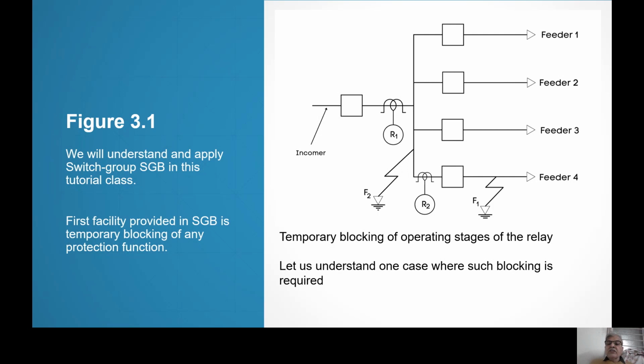So in the modern protection world, when quickness is a requirement, this relay offers that quickness, right? For that, you have to apply binary input. That is the requirement. For switch group blocking, you have to apply binary input. Binary input means there are two designated terminals on which you have to apply 230 volt DC. And if you apply 230 volt DC and use SGB, then R1 will block. If there is a fault at F2, then R1 will not block because R2 has not sensed. Right. So R1 will operate faster.